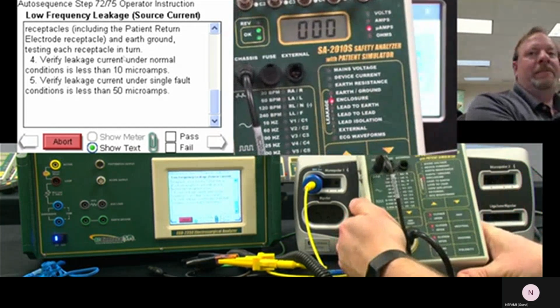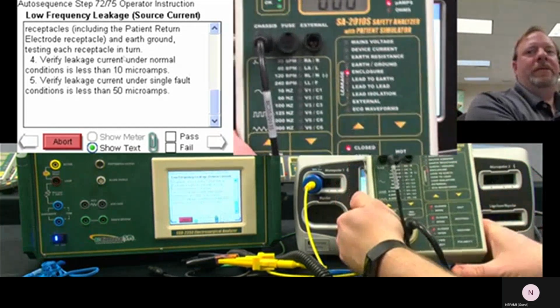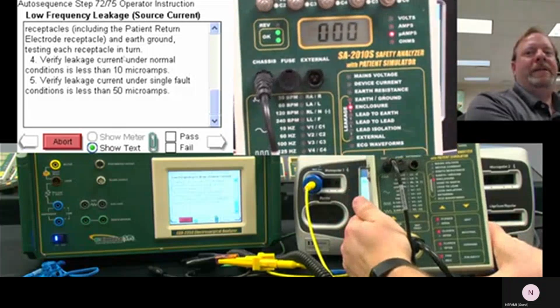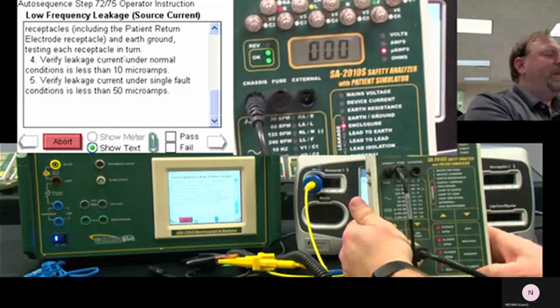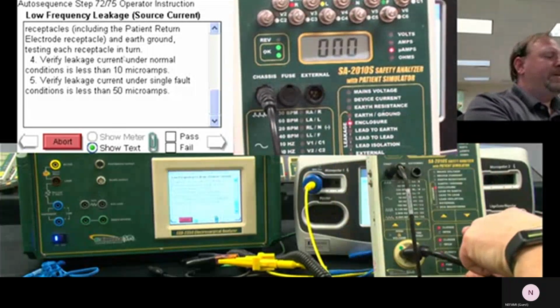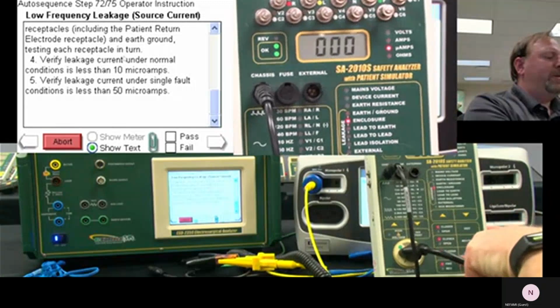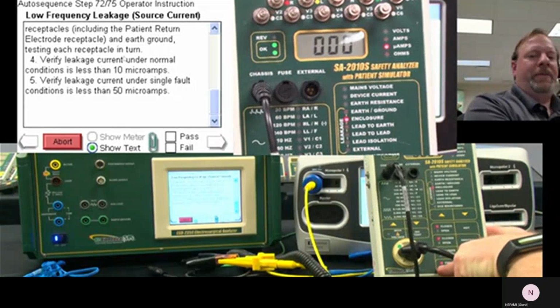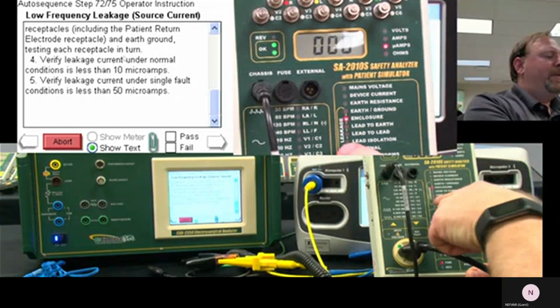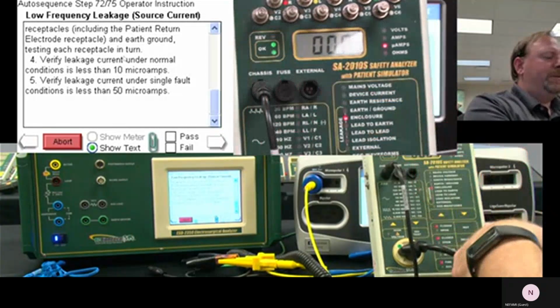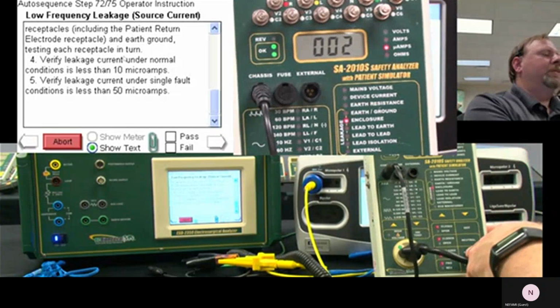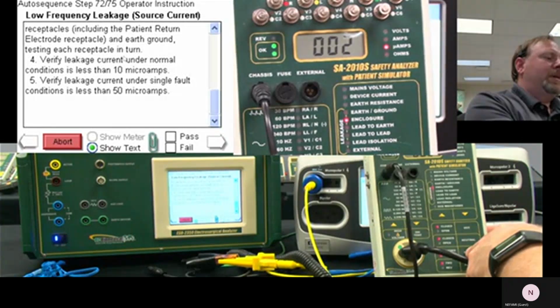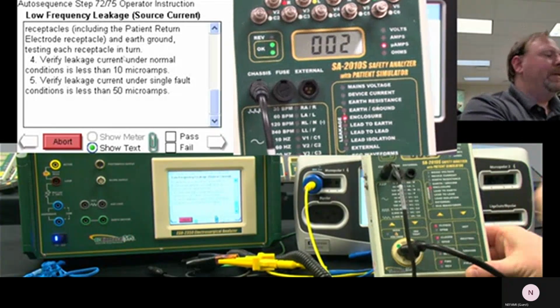So in this case, I guess you can kind of see the red there. But normal conditions is hot closed, neutral closed, ground closed, polarity forward. For the single fault condition, say it's an open ground. Oh, there we go, 2 microamps. So that's still well underneath our 50.